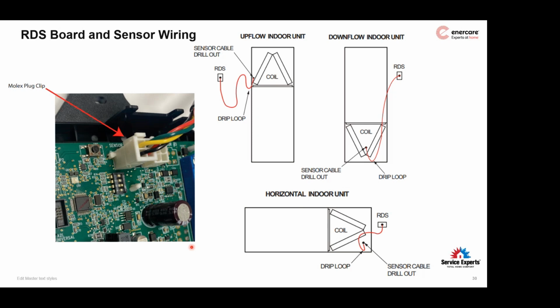The cased coil, if I'm not mistaken, on the left or right side will have a knockout already there for the harness to run out. So you guys don't even have to drill a hole. It'll be there when you're ready to put the sensor wire through it, when you're wiring these RDS controls up, whether it goes into the furnace or into the air handler. Yeah, just remember the drip loop. That's all.